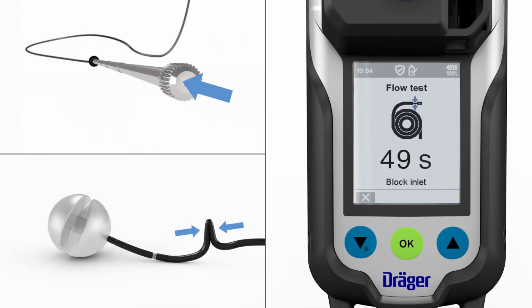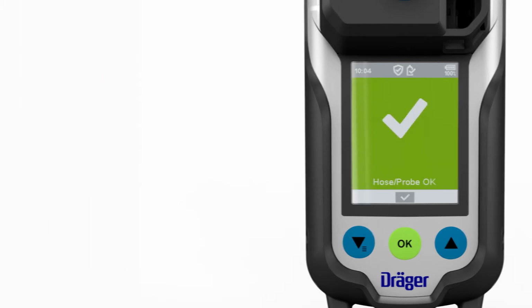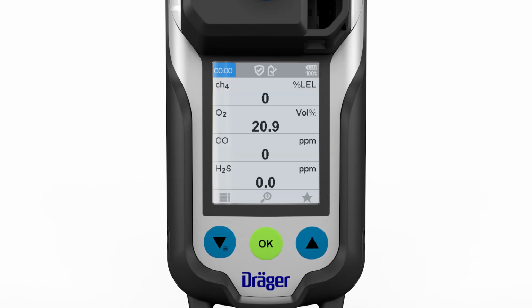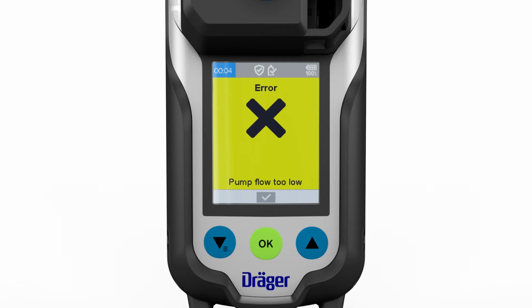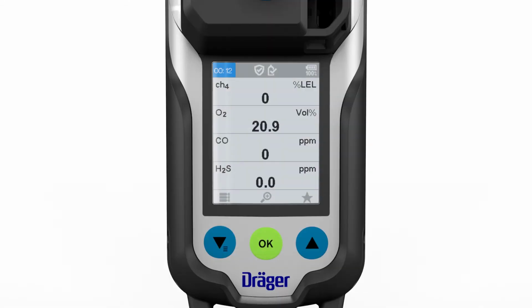Close the gas inlet at the end of the probe until the leak test is complete. Then release the gas inlet. If the leak test is successful, pump mode will be activated. If the pump test is unsuccessful, check the probe, hose and adapter as required and repeat the test. Once the device has passed the test, it is ready for operation in pump mode.